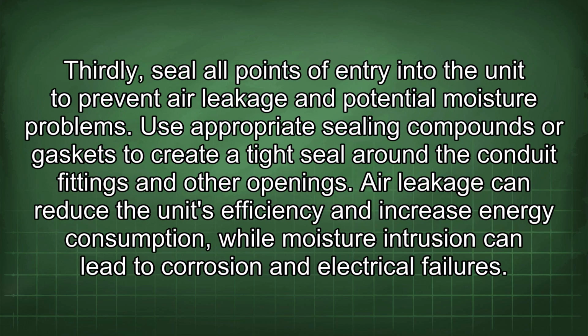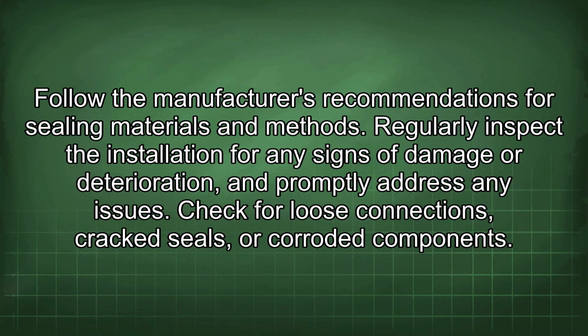Thirdly, seal all points of entry into the unit to prevent air leakage and potential moisture problems. Use appropriate sealing compounds or gaskets to create a tight seal around the conduit fittings and other openings. Air leakage can reduce the unit's efficiency and increase energy consumption, while moisture intrusion can lead to corrosion and electrical failures. Follow the manufacturer's recommendations for sealing materials and methods.